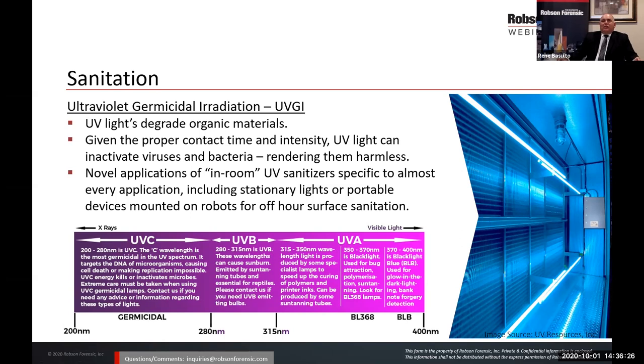So anybody who's been out in the sun understands that the UV rays or the light will degrade organic material. That's how we end up with sunburn. So given the proper contact time and intensity, right, we need to have the amount of time and the intensity while we're exposed to that light, the UV light can and will inactivate viruses and bacteria, rendering them harmless. So this is catching whatever went through the coil, catching it and hopefully rendering it harmless and reducing that risk. So that's the end result, or the end goal, is to reduce that hazard. So this is doing it.